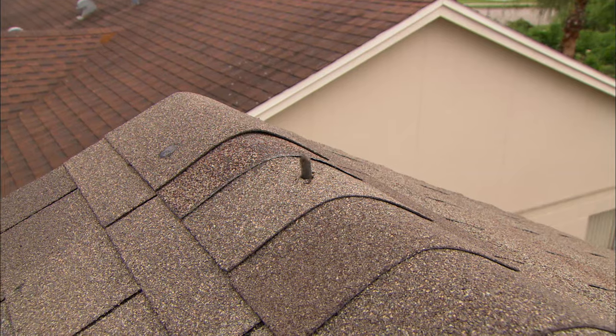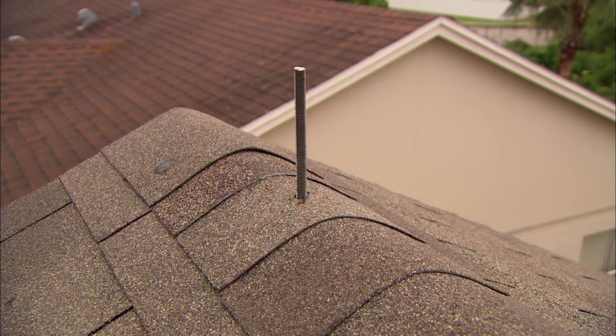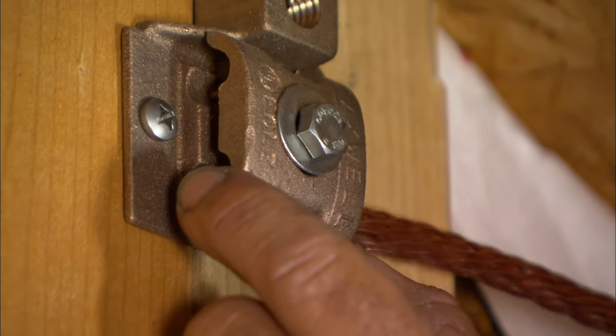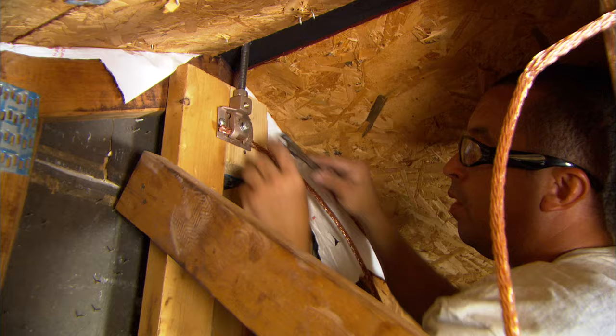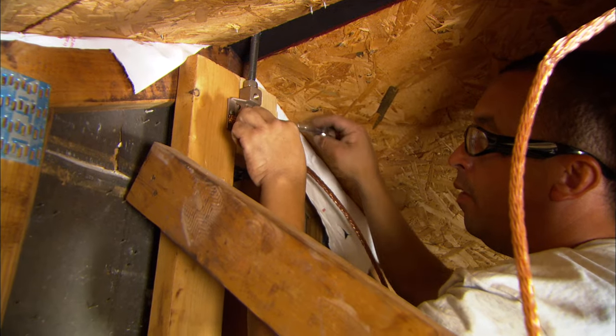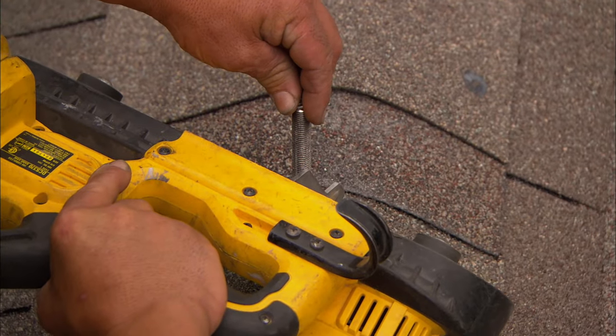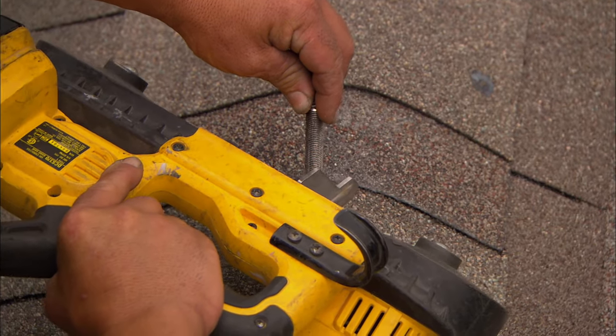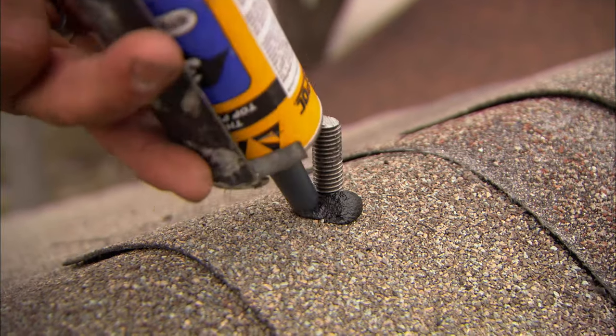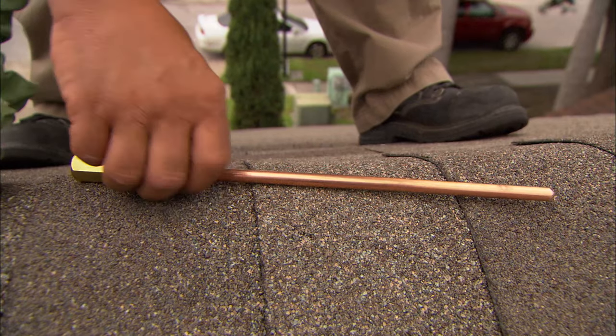We'll drill a half-inch hole through the ridge and install a through-roof assembly. It's really important the ridge cable is securely fastened to the base plate. We'll cut the thread rod to the proper length, seal it with roofing cement, install a nut and washer, and the lightning rod just screws on top.